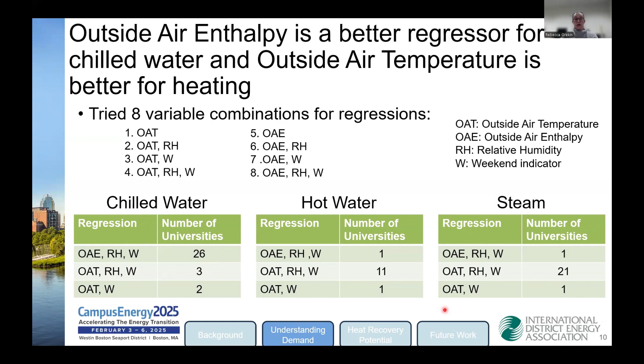Whereas for both hot water and steam, the best regressor for the largest number of universities is actually outside air temperature, along with relative humidity and weekend indicator. It's quite interesting that for chilled water, outside air enthalpy matters much more than outside air temperature, whereas for heating - hot water and steam - outside air temperature is the largest variable.